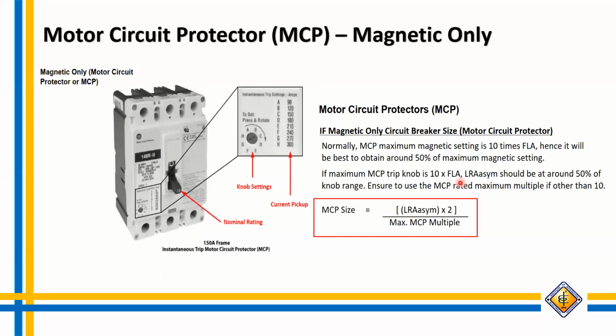So this one is the MCP. How to size the MCP? You have to calculate the locked rotor asymmetrical current multiplied by 2, divided by the maximum MCP multiple, which is typically 10. Okay, if the maximum MCP trip knob is 10 times FLA, or the full load ampere, the setting should be around 50% of the knob range. So you can use this one as a reference in the settings of your MCP.